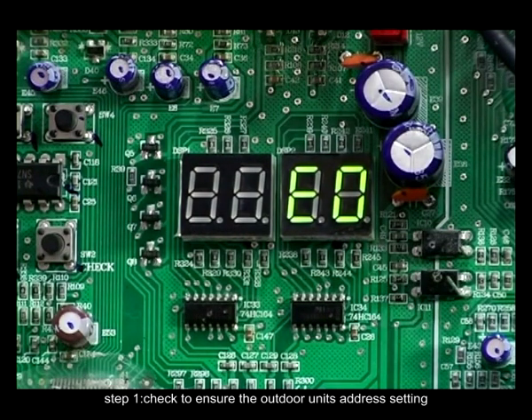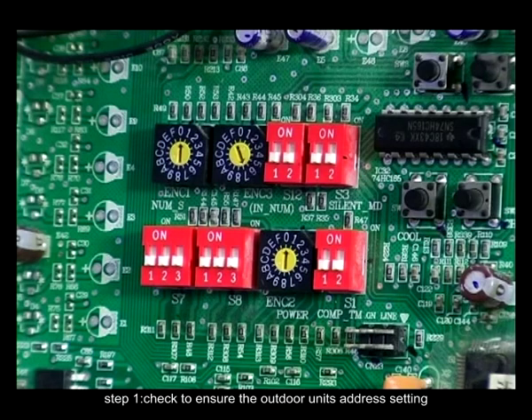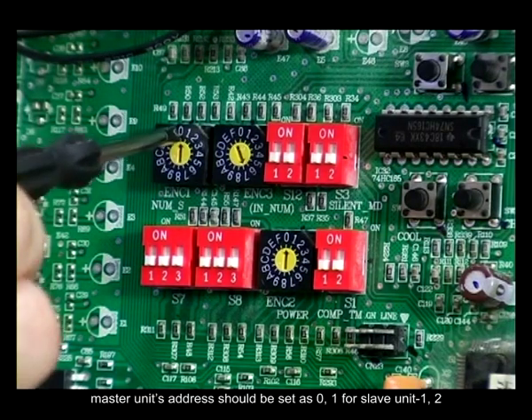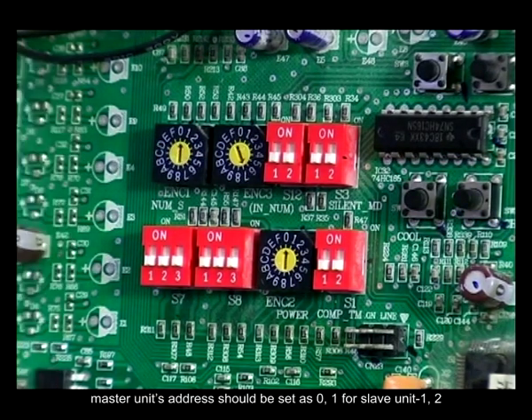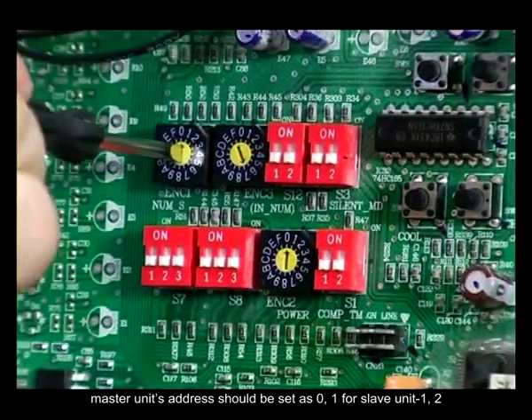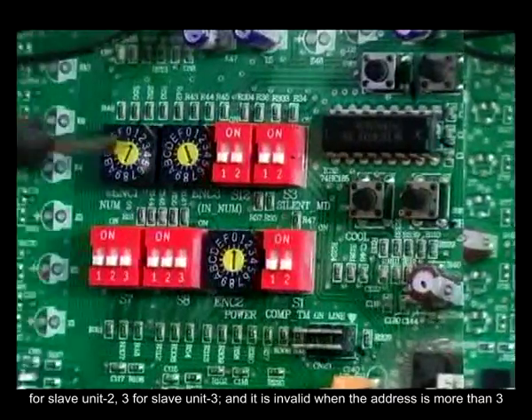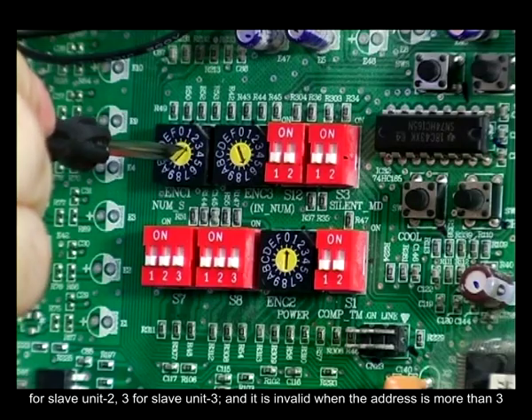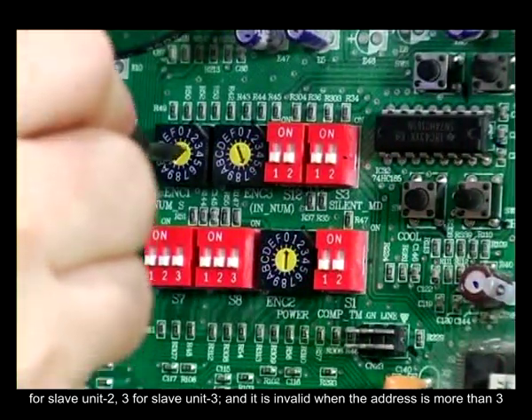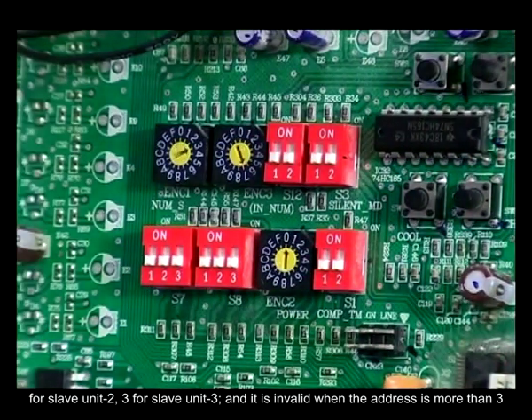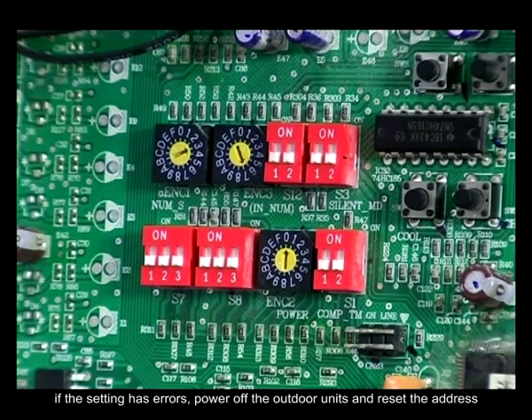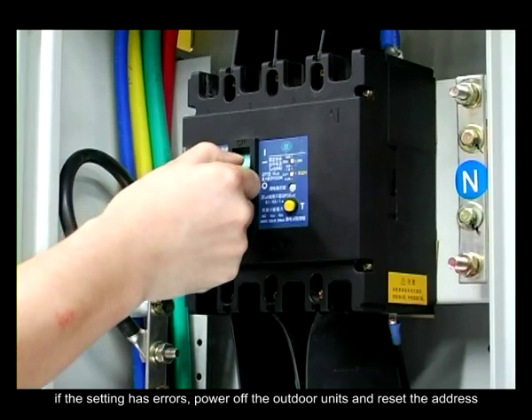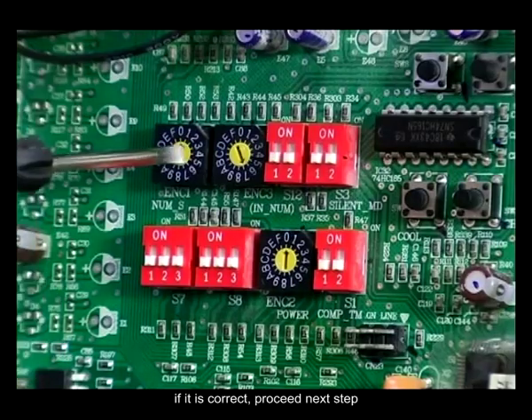Step 1. Check to ensure the outdoor unit's address is set correctly. Master unit address should be set as 0. 1 for slave unit 1, 2 for slave unit 2, 3 for slave unit 3. And it is invalid when the address is more than 3. If the setting has errors, power off the outdoor units and reset the address. If it is correct, proceed to next step.